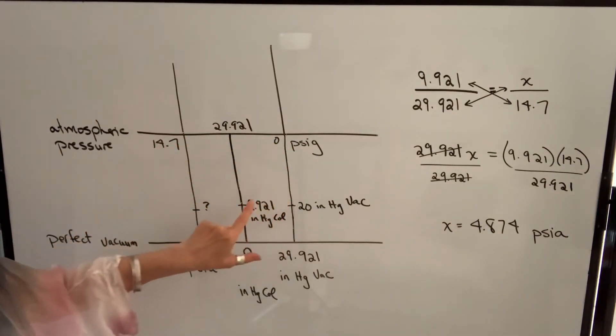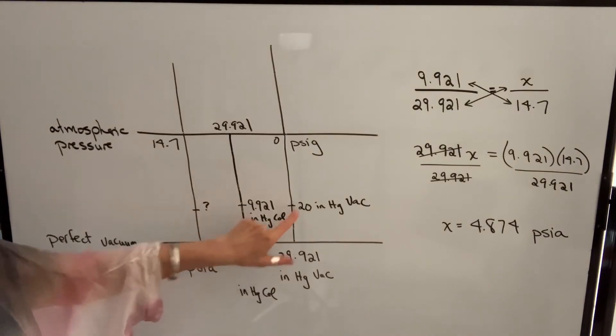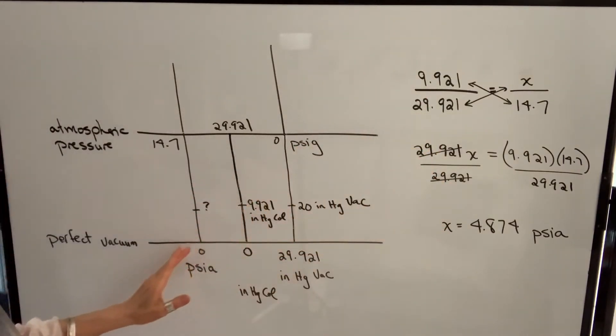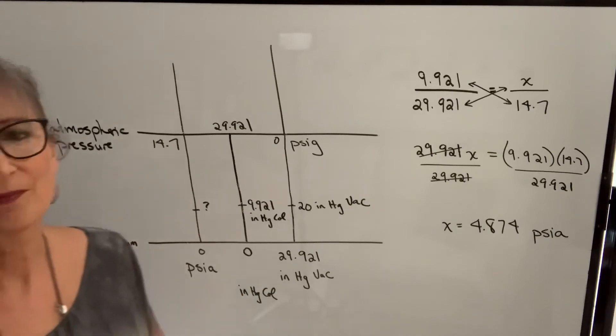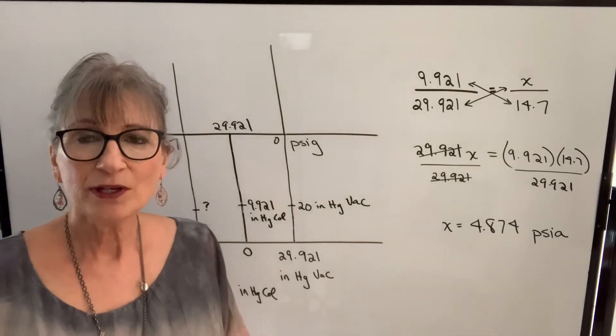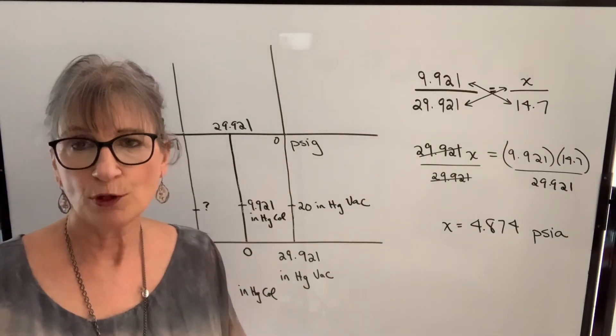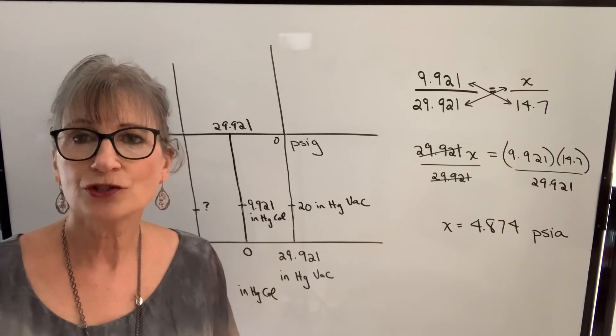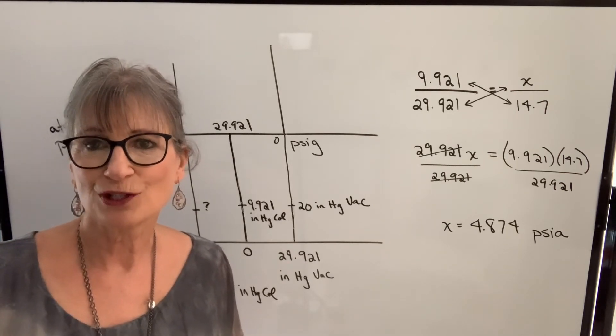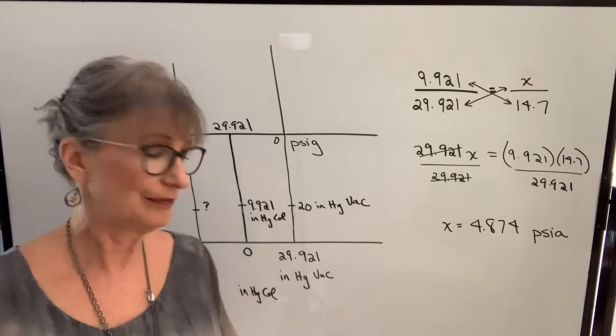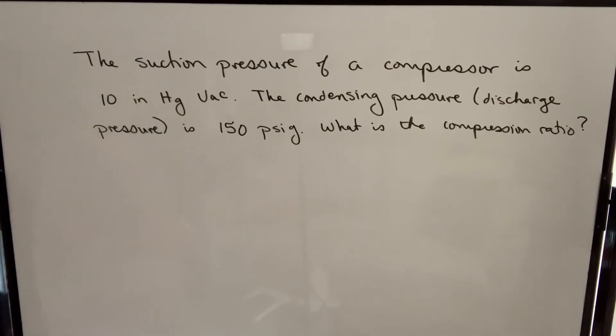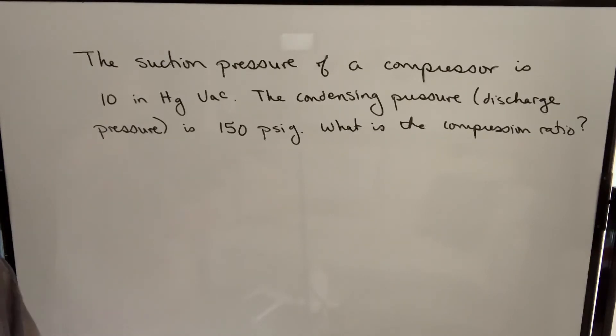That method works whenever you have a vacuum pressure and need to change it to PSIA: take the intermediate step of changing to inches mercury column, then use proportion to find PSIA. Now that we know how to convert both gauge pressure and inches mercury vacuum to PSIA, we can calculate compression ratio. Here's an example: the suction pressure of a compressor is 10 inches mercury vacuum, and the discharge pressure is 150 PSIG. What is the compression ratio?